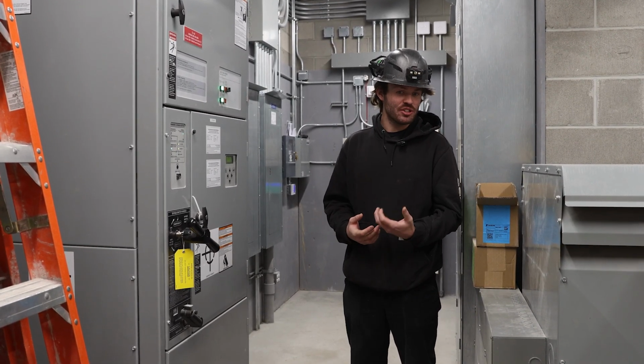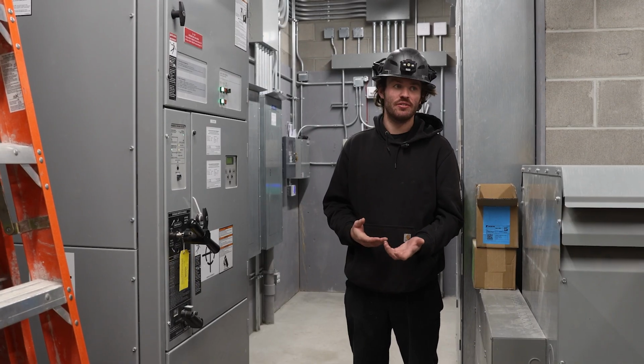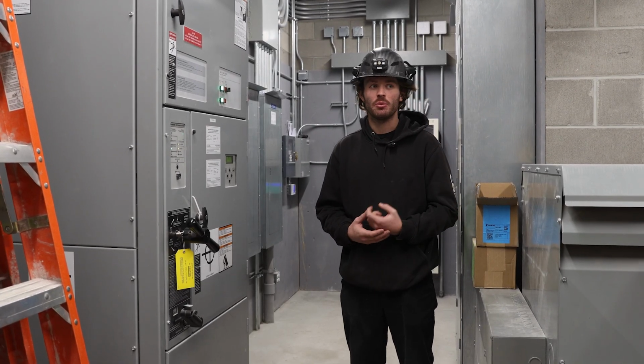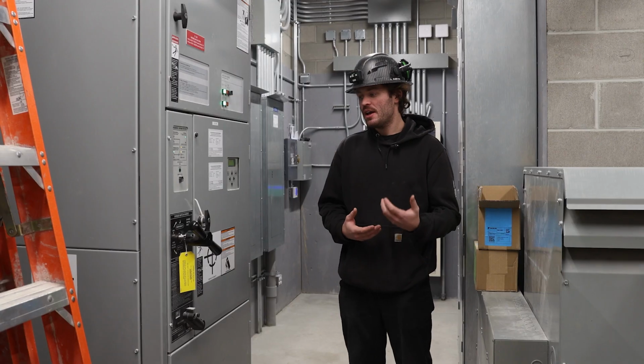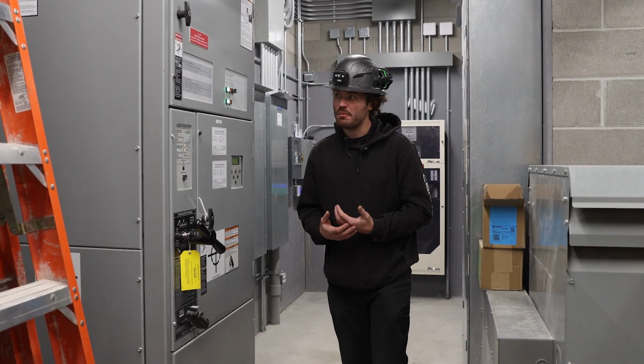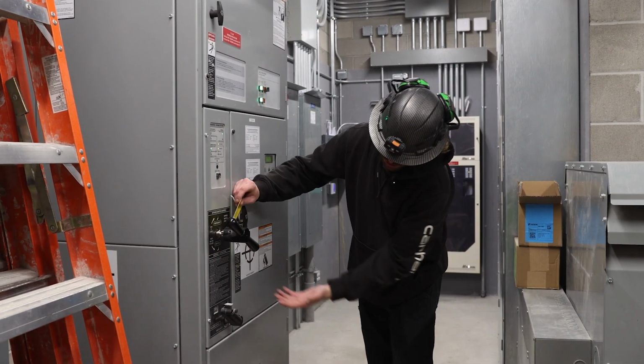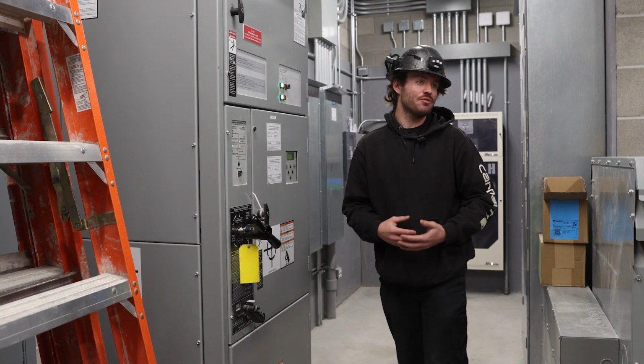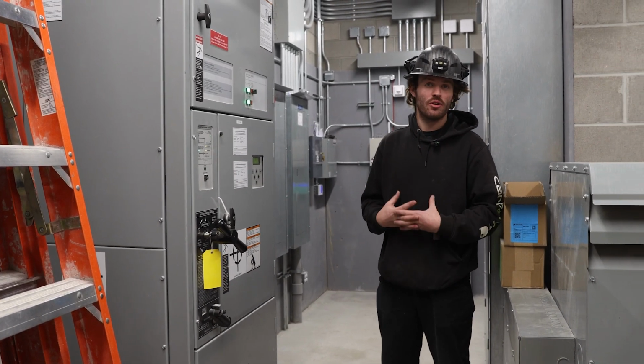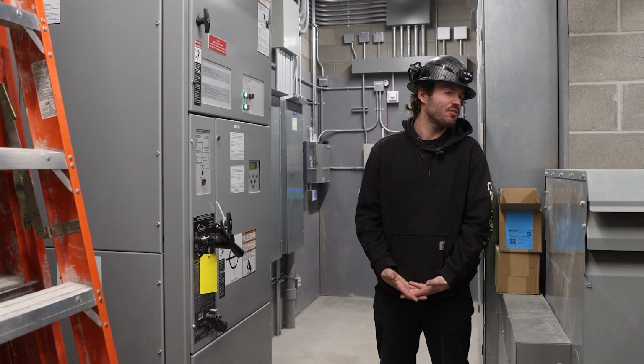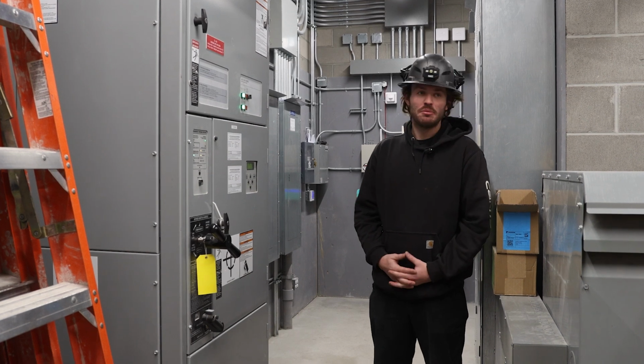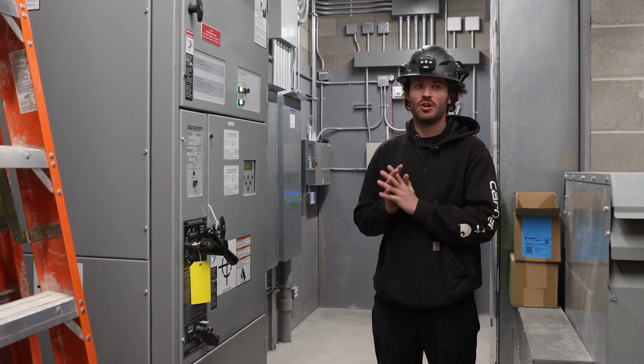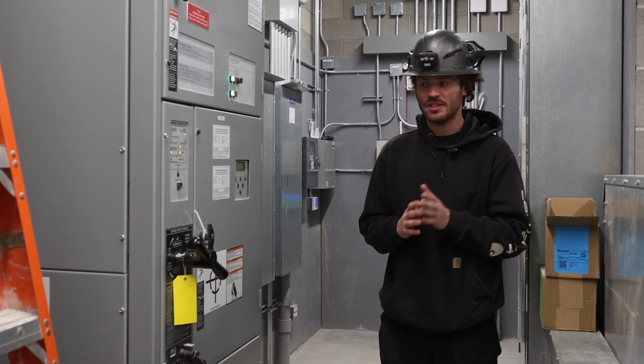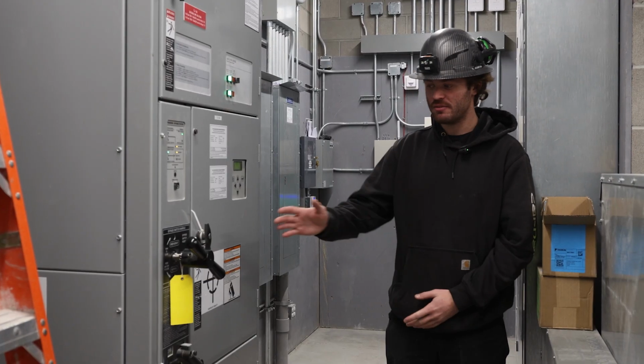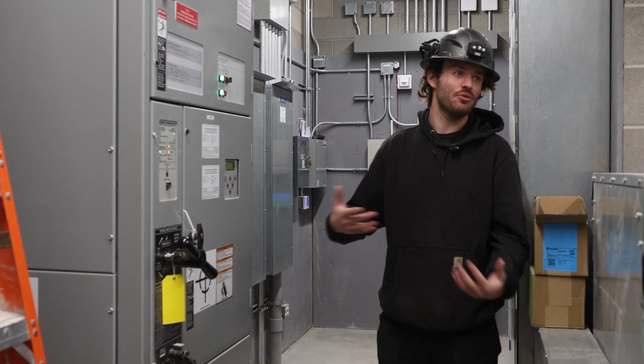Bypassing it will only generally be done during service work, so it's not something that you will regularly have to encounter. If it is something that comes up, the instructions are written on it, and feel free to contact us or your generator service provider for guidance if it were to happen. It can only be bypassed into the source that it's already in. That's an important detail, but it covers all that and it interlocks what you can and can't do.